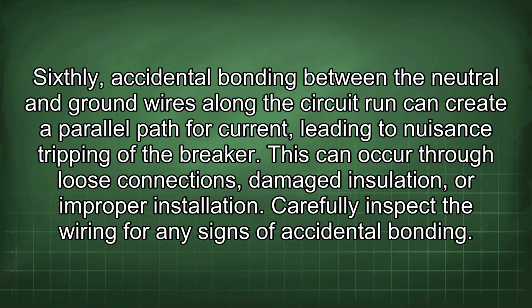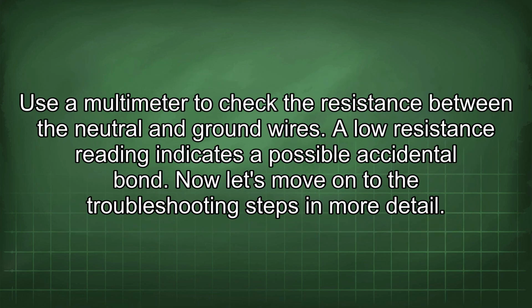You can also use shielded cable or run the conductors in separate conduits to reduce inductive coupling. Sixthly, accidental bonding between the neutral and ground wires along the circuit run can create a parallel path for current, leading to nuisance tripping of the breaker. This can occur through loose connections, damaged insulation, or improper installation. Carefully inspect the wiring for any signs of accidental bonding. Use a multimeter to check the resistance between the neutral and ground wires. A lower resistance reading indicates a possible accidental bond.